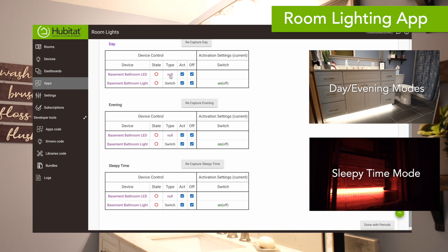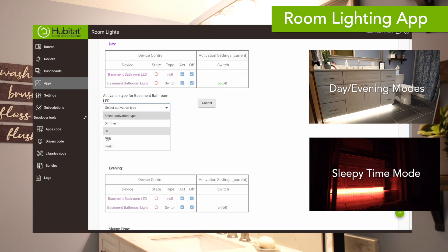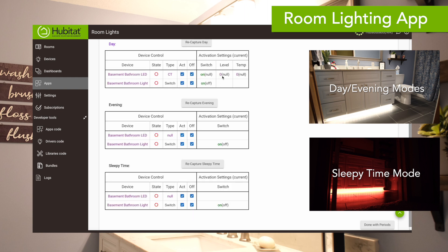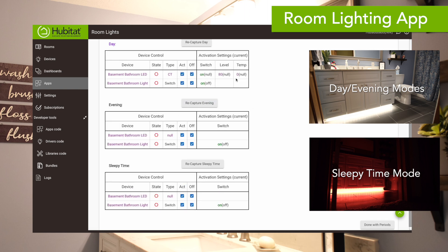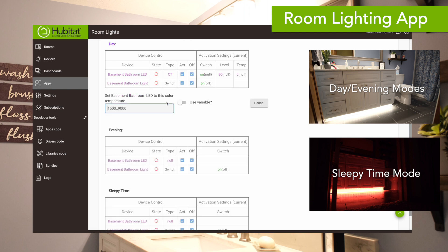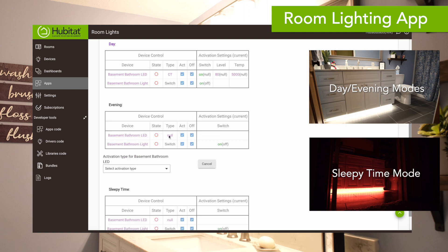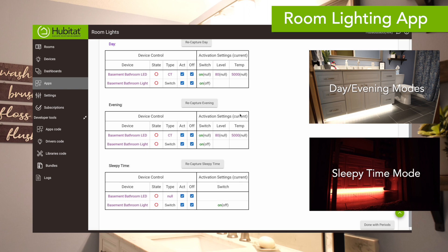We'll start with the day mode — day and evening are going to be the same. The type is CT, which is color temperature LED. For day and evening, we're going to set the level to come on at 80%. The color temperature is going to match the color temperature of our light bulbs in that room, which is 5,000K. So when activated during the day, the basement LED lights turn on at 80% with 5,000 Kelvin, and the basement bathroom light on a switch will turn on as well. We'll match these same settings for the evening mode.